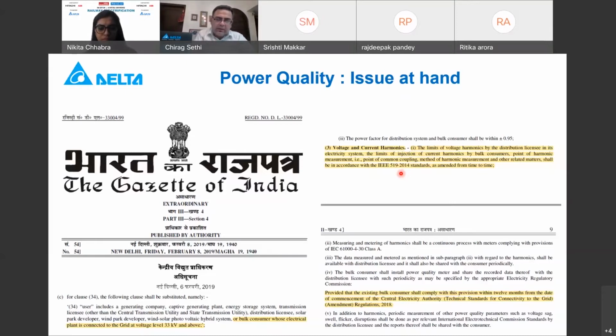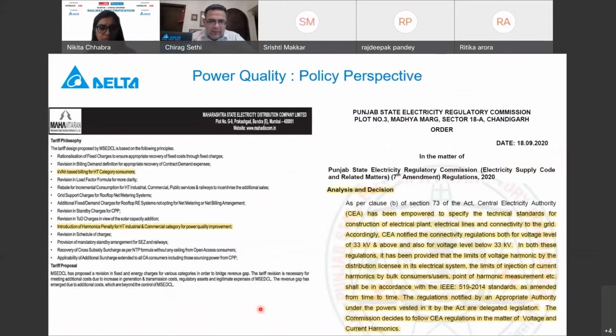So this regulation is slowly, but now at a faster pace, getting translated into state-level regulation, where different states are now incorporating this requirement in their draft code and gradually into a formal regulation. We already are aware that some states, including Punjab as well as Maharashtra. The Maharashtra one is more recent, I think early this year, the MERC, Maharashtra Electricity Regulatory Commission, came up with a similar requirement, reiterating that compliance with the IEEE 519 standard is to be followed by all bulk consumers so that harmonics are not pumped into the grid, whereby the source side gets polluted.